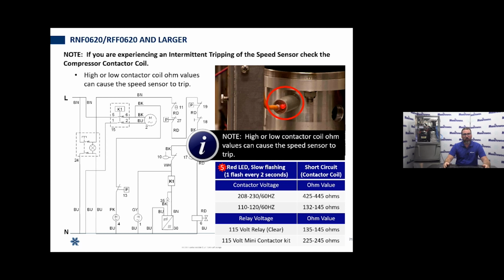So if we see that condition, the first thing I would do is get out my meter, take an ohm reading across the motor contactor coil. We're going to make sure that we don't have either excessively high resistance or excessively low, so something like 1, 2, or 3 ohms. We do have a specification chart. You can see that on the screen here, based upon whether or not it's a 208 or a 110 voltage machine, or if you have a remote condensing unit option, you're going to have a little bit different system, which we'll talk about. They're going to have a relay coil that's controlling a liquid line solenoid. But we do have values to look for. But what I like to stress, too high resistance, too low resistance, we have something wrong with that contactor coil. Or another possibility is if we have resistance to ground.